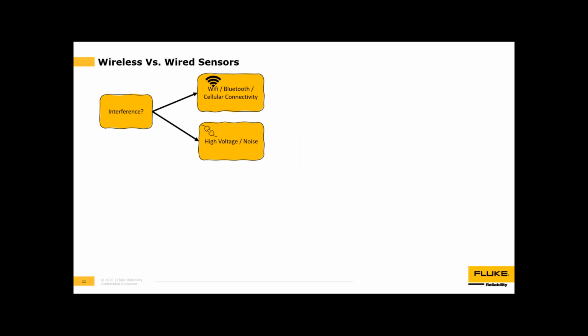One of the top things to consider when looking at these sensors is interference. With wireless sensors, depending on the protocol—Wi-Fi or Bluetooth—you need to pay attention to where they're installed. If they're talking to a gateway, a concrete wall or metal frame in the way can cause interference that needs to be considered.